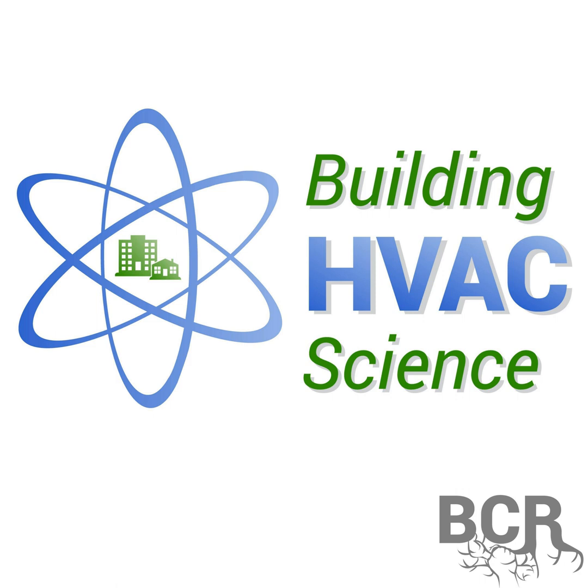Yeah, so that goes along with the scheme that you developed in the first topic of filtration. Right. So when we're designing systems, whether it's new or existing construction, we use the same room to hallway pressure standard that's in the Energy Star program, and I think several other state level programs. That's a 3 Pascal pressure differential as the maximum that we allow between a bedroom and the hallway when the doors are closed and the air handler is running on high speed. If we have more than that, then we know we need to add a transfer grill or jumper duct or something like that. Through our diagnostic testing, we know what works and what doesn't work, which is really handy.